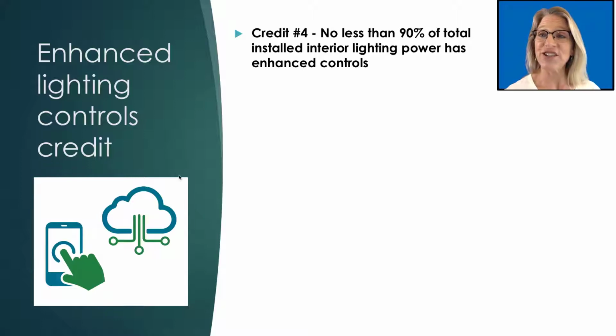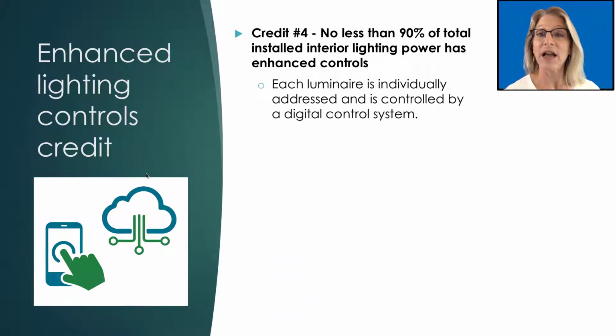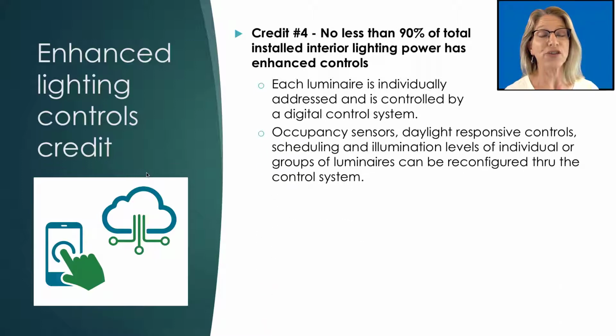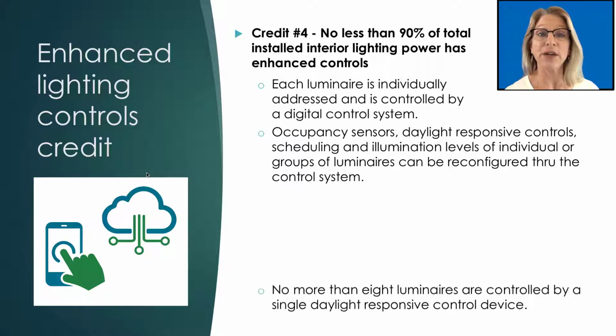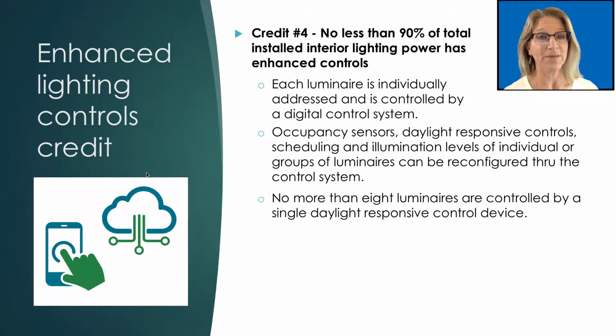There is an additional efficiency package credit for enhanced lighting controls. In a nutshell, a project may be eligible for this credit if each luminaire is individually addressed and is controlled by a digital control system. It is required to have occupancy sensors, daylight responsive controls, scheduling, and illumination levels of individual or groups of luminaires that can then be reconfigured through the control system. It states that no more than 8 luminaires may be controlled by a single daylight responsive control device.